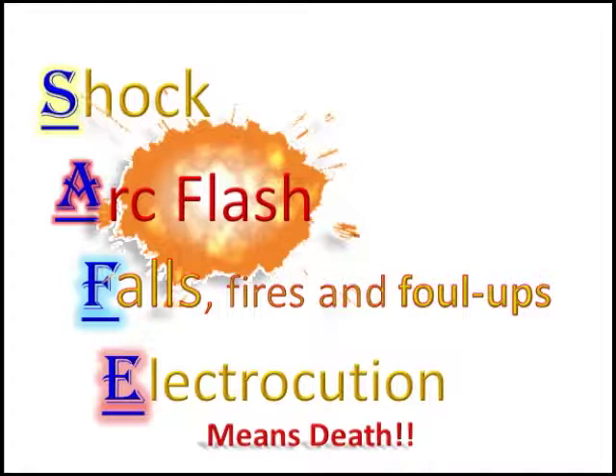Our next hazard is the risk of arc flash or arc blast. Now, an arc flash doesn't last very long, about a second. But in that second, temperatures can reach anywhere from 10,000 to 35,000 degrees Fahrenheit. And pressure waves can be delivered anywhere between 100 and 200 pounds per square foot.